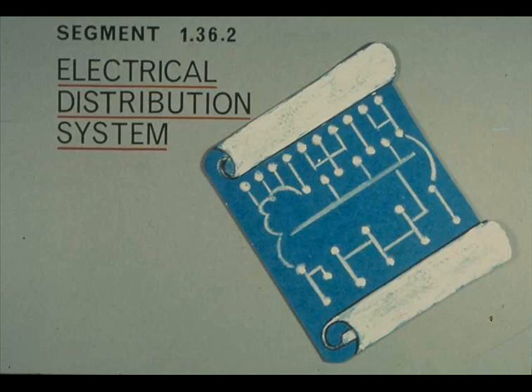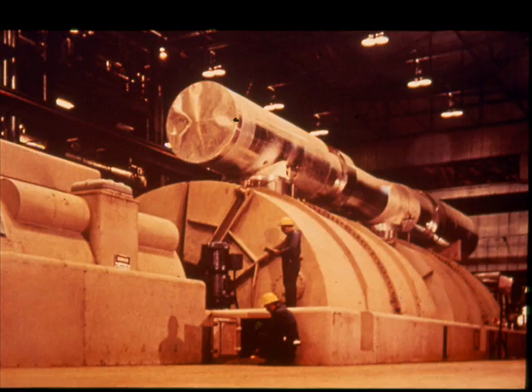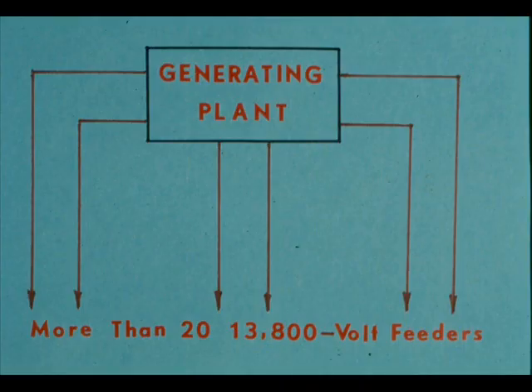For greatest efficiency in your operation of electrical equipment, you must know the electrical distribution system of your refinery or plant. Some industrial plants generate all or part of the electricity they use; others buy it from a utility company. In either case, there is at least one relatively high voltage feeder line from the generating plant or from a power transmission line. The number of feeders and the voltage they carry depend on your plant's needs. In one large refinery, more than 20 feeders carry 13,800 volts to various parts of the plant.